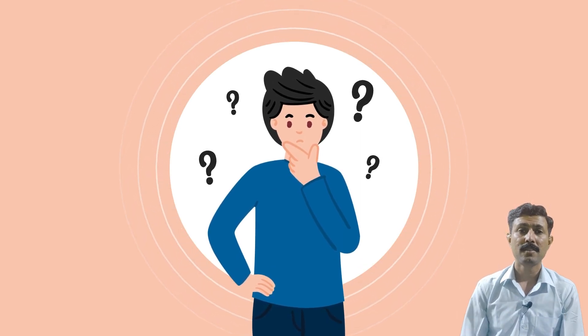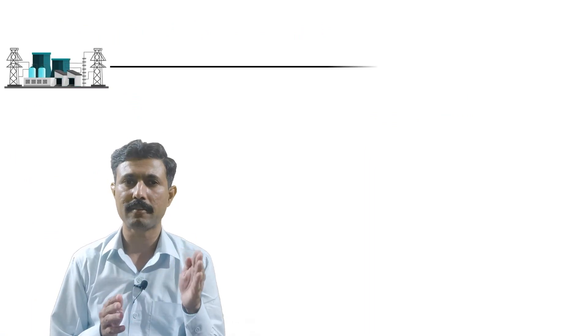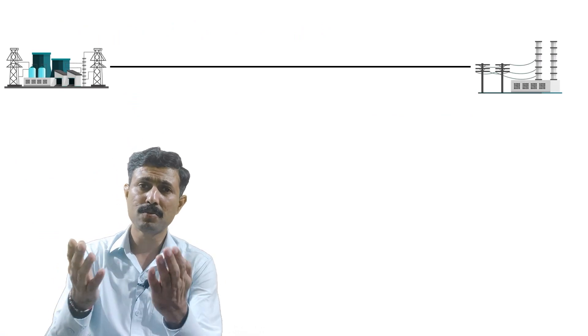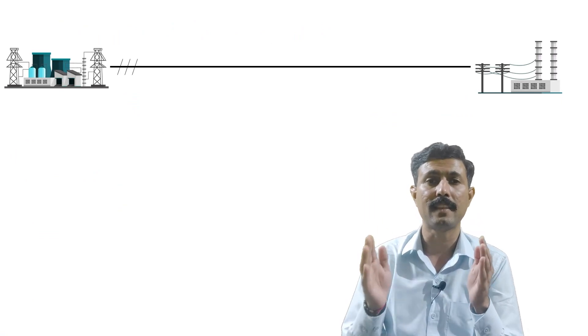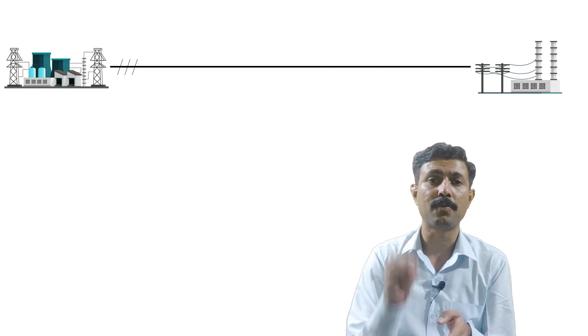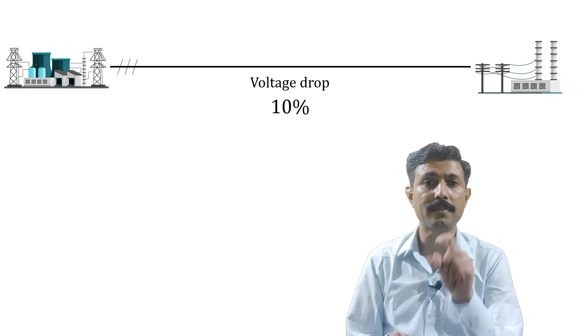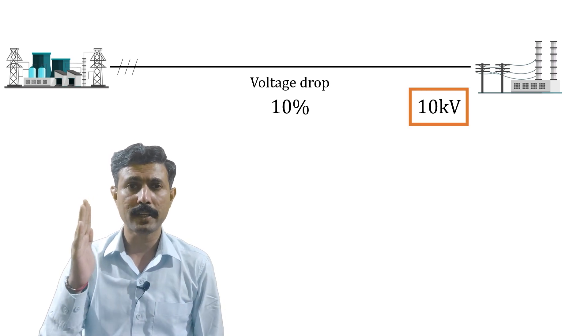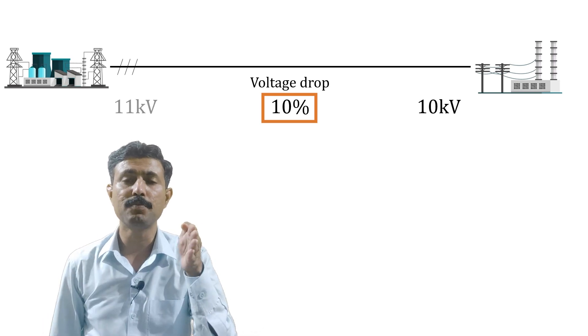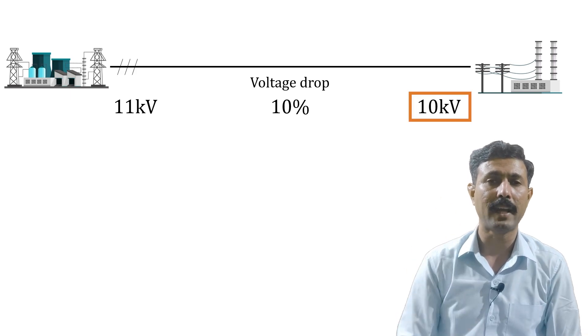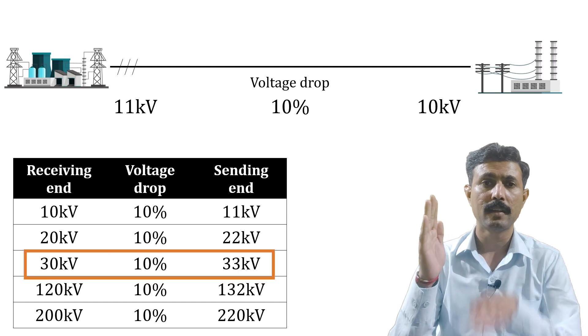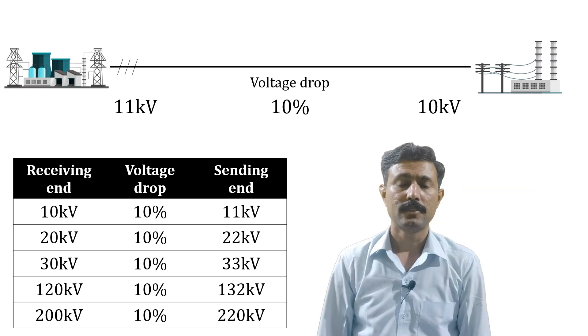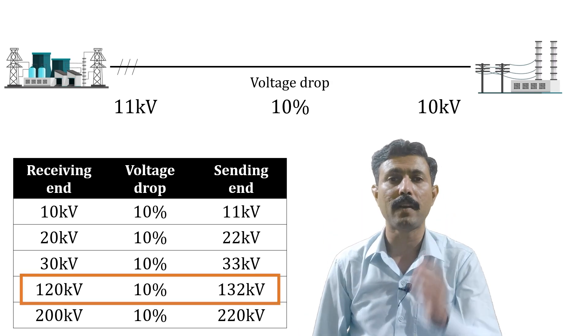Then the next question comes — what is the real reason behind this? Now let's understand another reason with this example. Generally, the generating station is far away from the load side — a long distance between the generating station and the load. Because of this long distance, there will be some voltage drop. The allowable limit of that voltage drop is 10%. So, for example, if I want to receive 10 kV at the load side, I add 10% voltage drop, giving 11 kV to send. If I want to receive 30 kV, plus 10% drop gives 33 kV. Likewise, if I want to receive 120 kV, plus 10% drop gives 132 kV.